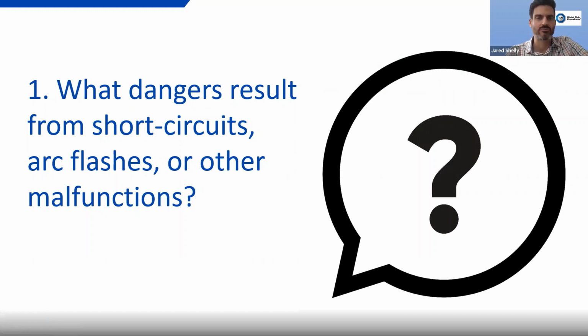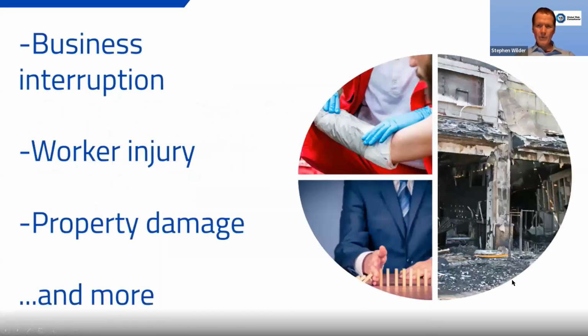What are some dangers that can happen when electrical systems experience short circuits, arc flashes, or other malfunctions? Well, thanks for having me here. There are 3 studies that we typically do in one report. It's a short circuit, a coordination, and an arc flash study. The short circuits can cause fires, heat, pressure, personal injury. Coordination failures generally don't cause fires or personal injuries, but they can cause significant downtime. Arc flashes can cause significant property damage and personal injury.